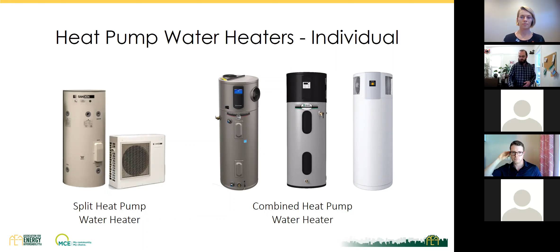There are some particular nuances when doing these in multifamily buildings. Those water heaters are typically located in internal or external closets, and sometimes they tend to be a little small. So there might be ducting or space constraints there that you'll have to think about. Potentially also there's limited electrical panel capacity and breaker space. So again, that's something you need to ID. Make sure that you have sufficient space in your panel. They can potentially have more complexity for dedicated circuit runs.